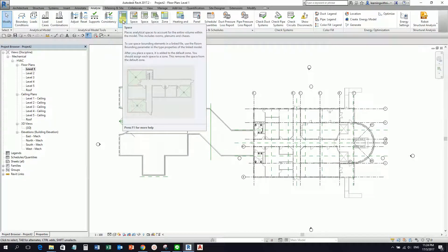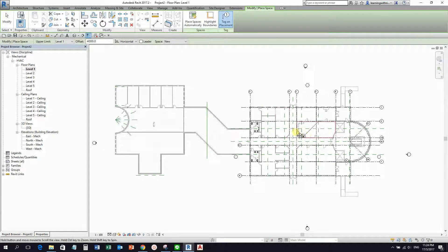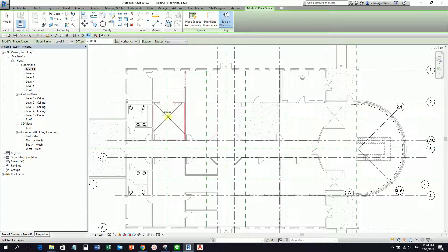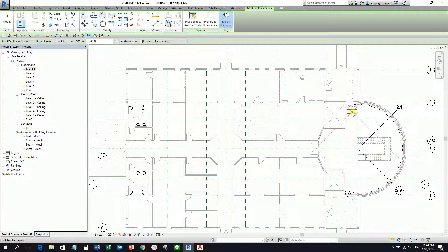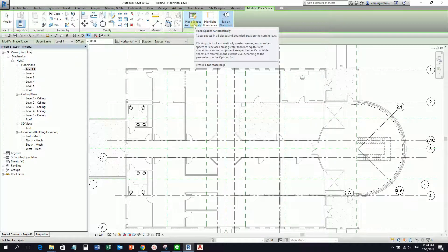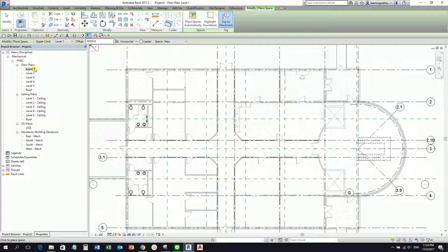So I'm going to select the Space tool. As you move your pointer, you will notice — if the architect created the model nicely — you'll be able to place the spaces here correctly. You can place them one by one or you can select Place Spaces Automatically. If you check the options bar, I am at level one. The upper limit is level one. Let's say I want to place the space from level one to level two, so I'm going to change the upper limit to level two and make the offset zero — meaning the space will extend from level one to level two.